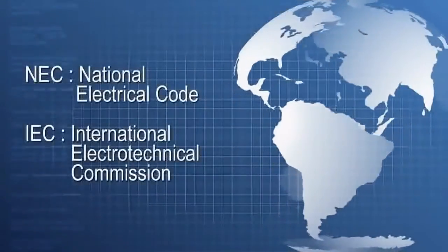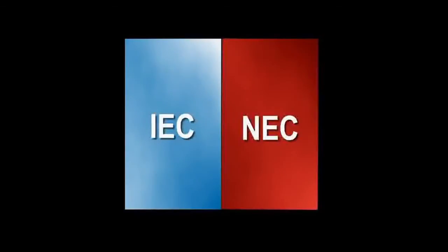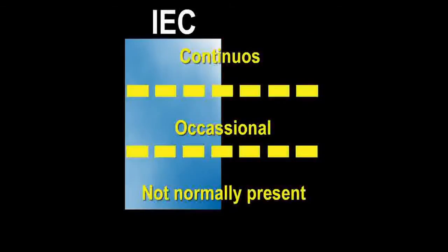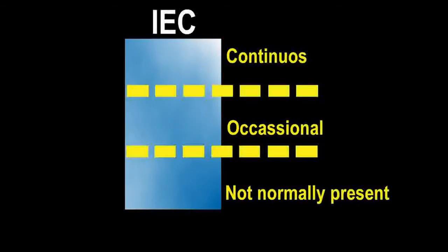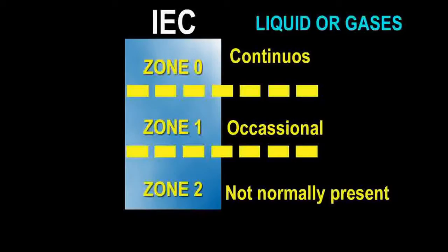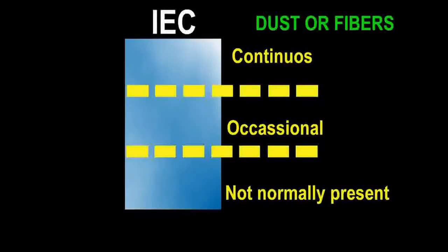The two predominant methods used for classification of hazardous environments are the NEC and IEC standards. Both classify the level of risk into three main categories: continuous, occasional, and not normally present — all three reflecting the likelihood of an explosive atmospheric condition. Within the IEC standard, the general risk categories are classified as zones, reflecting the physical material that could provide a potential fire or explosion. For liquids and gases, the area classifications are zone 0, zone 1, and zone 2. By altering the physical material to dust or fibers, the area classification changes to zone 20, zone 21, and zone 22.